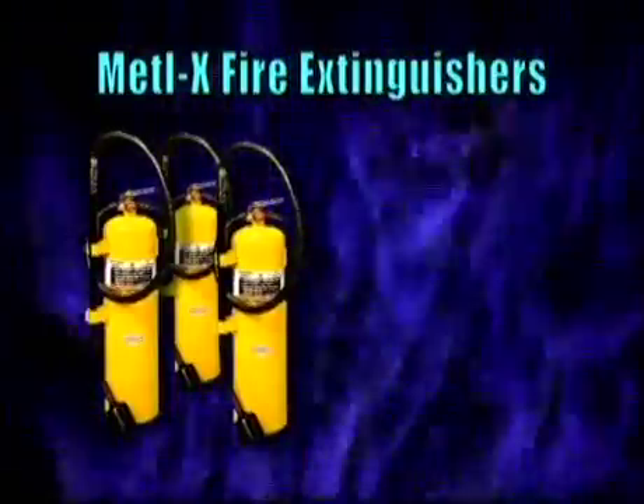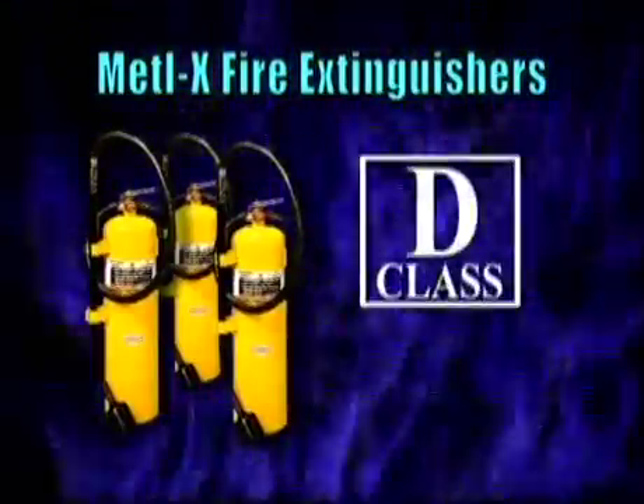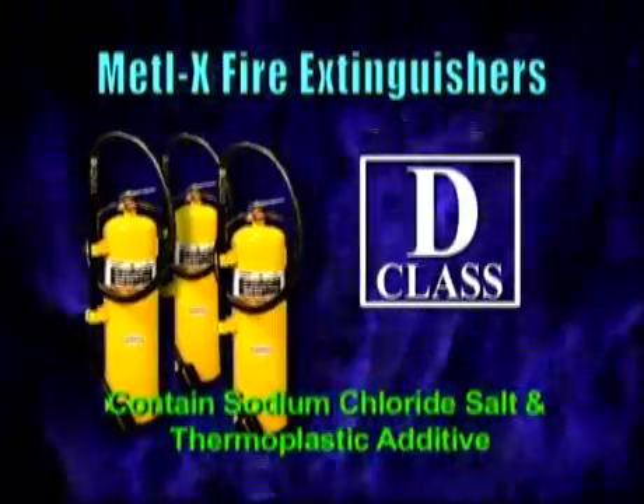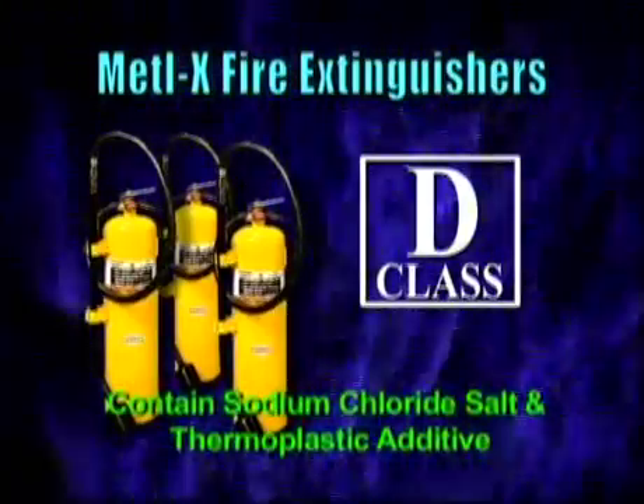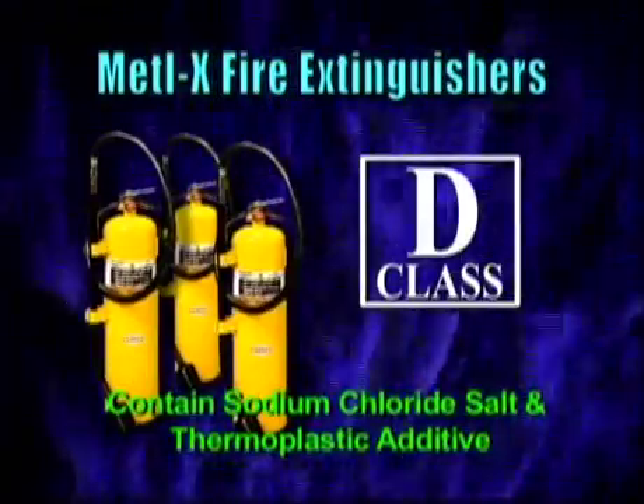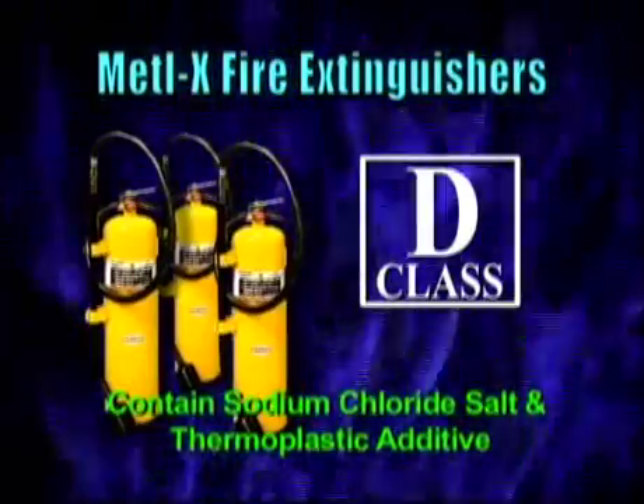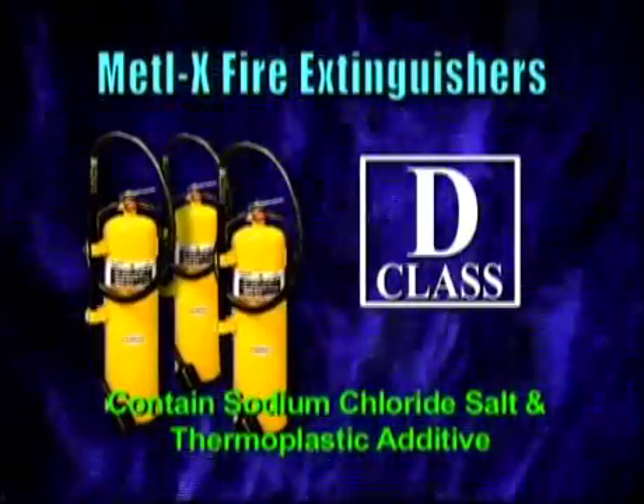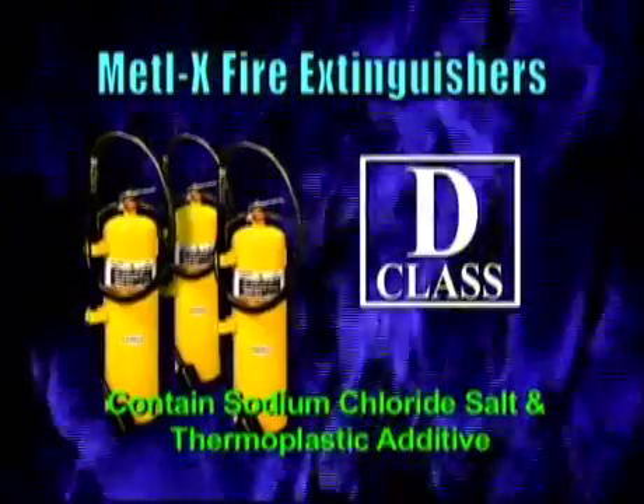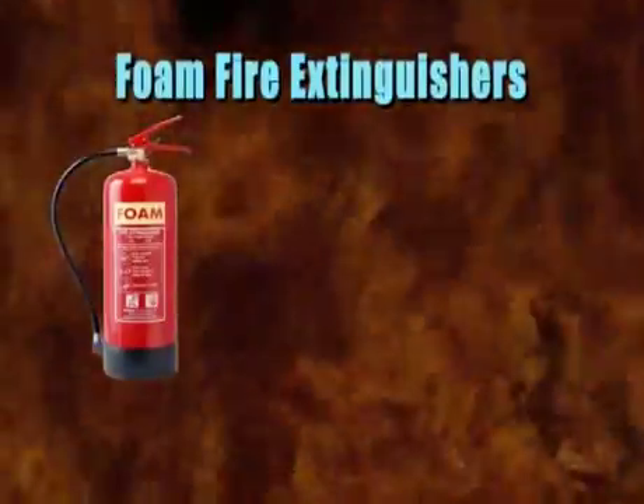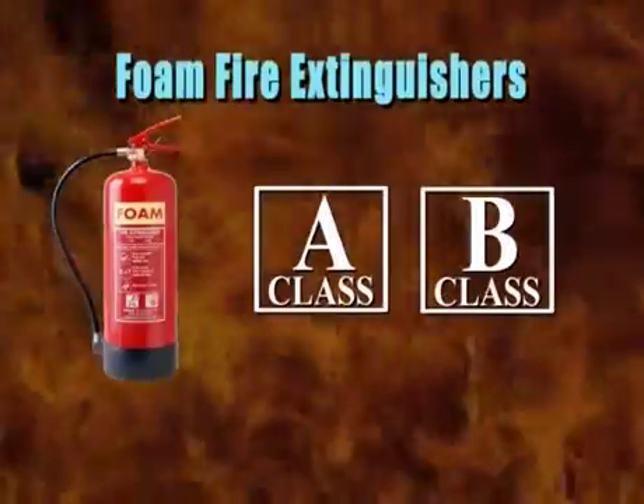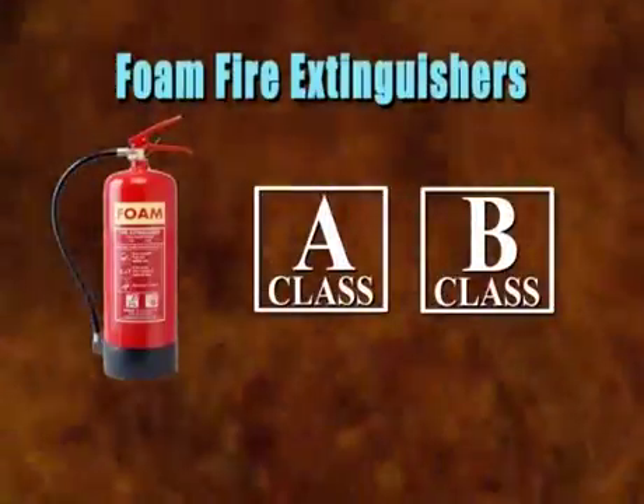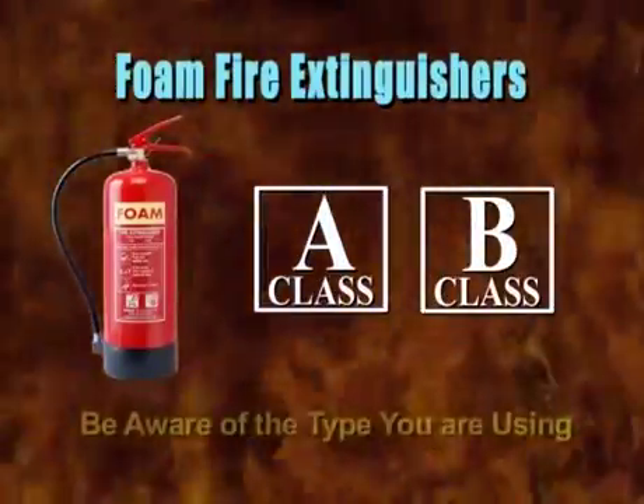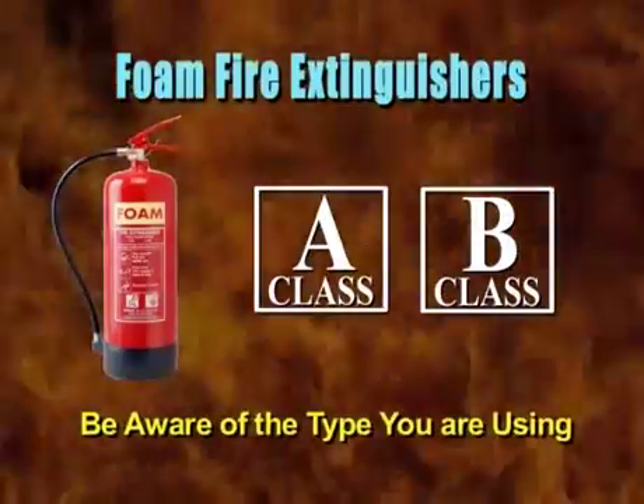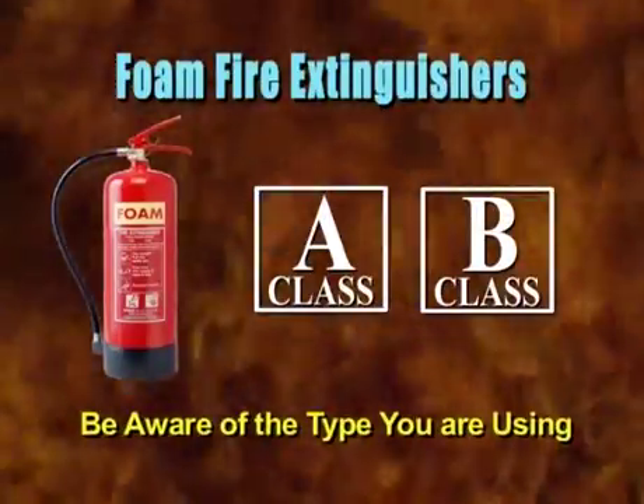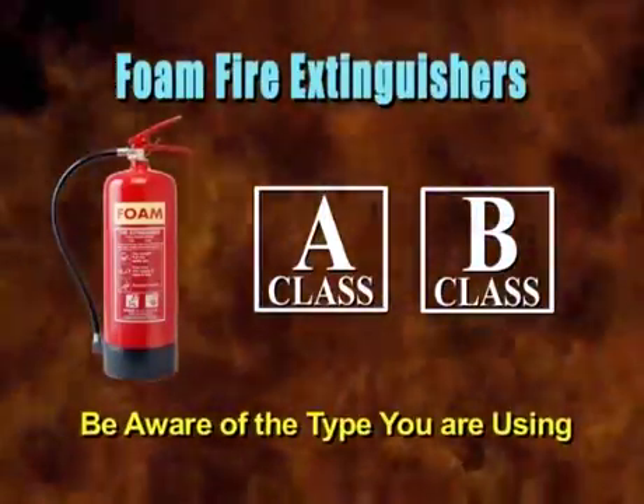Metl-X extinguishers are to be used on Class D fires and contain sodium chloride salt and thermoplastic additive. Plastic melts to form an oxygen-excluding crust over the metal, and the salt dissipates heat. Foam extinguishers are for use on Class A and B fires only. There are different types of foam extinguishers, and you need to be aware of which type you are using and its proper use and limitations.